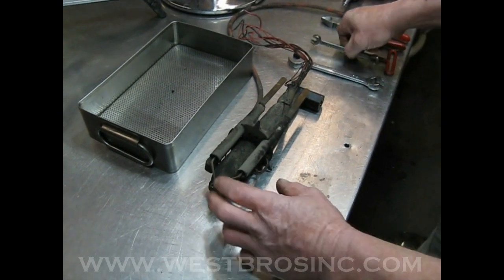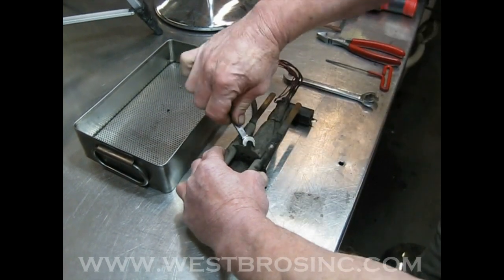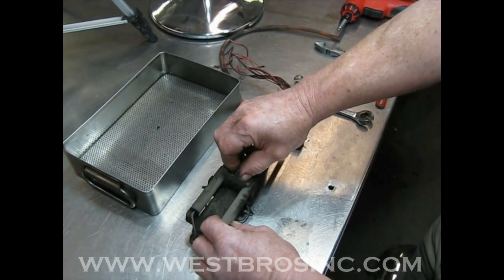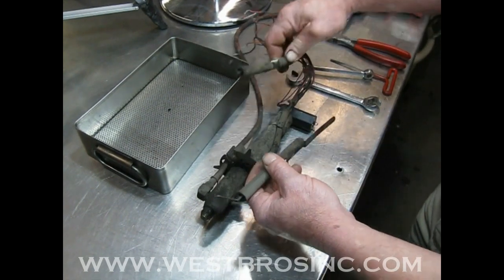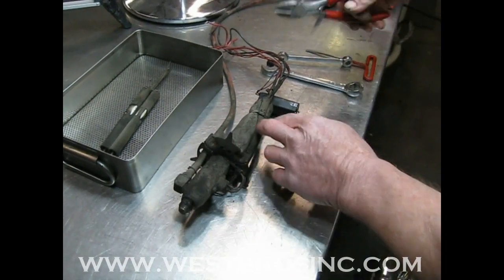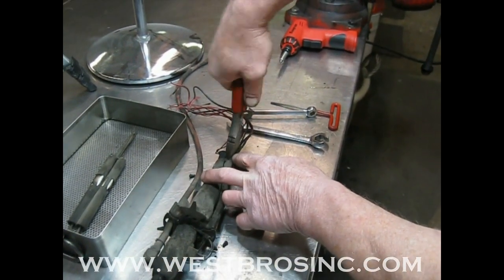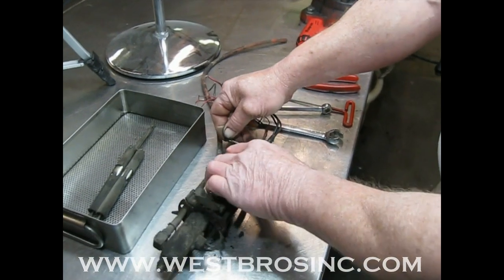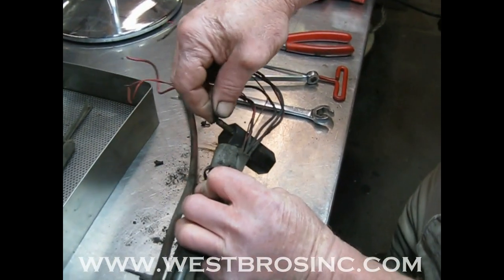This one's a bad one. Carefully remove the electrodes — they are fragile. Carefully remove the small preheater cartridge from the inlet preheater block.